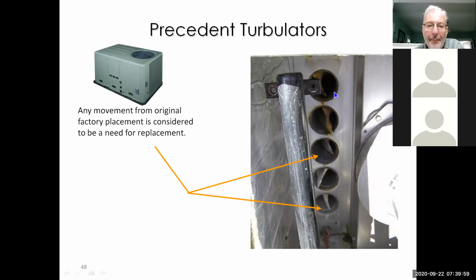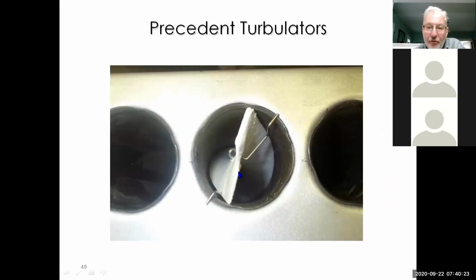But if you go on a job and you see the turbulators are discolored or they're pushing in like this, that needs to be corrected. Eventually what'll happen is they'll push in far enough that they'll start to crumble and fall apart, and then they tip the flame in a downward direction, and then they start to take the heat exchangers out. So when you're looking at these turbulators, they should be to the edge like this. This little stainless steel clip should be holding them in place. And if they're not, take them out, replace them, and make sure that they're in good condition so that we don't have any heat exchanger issues.